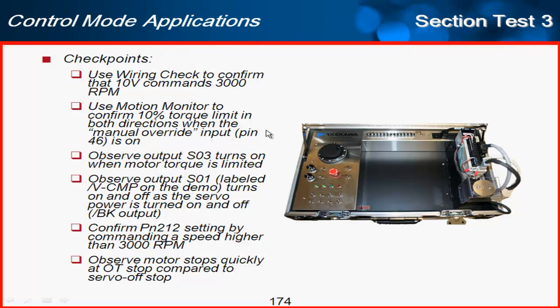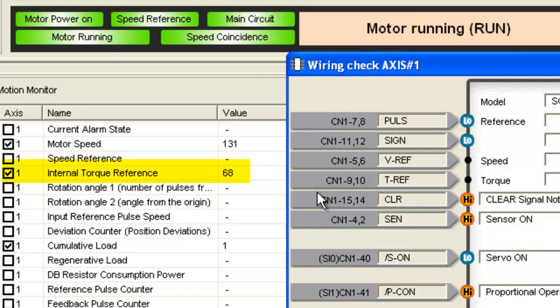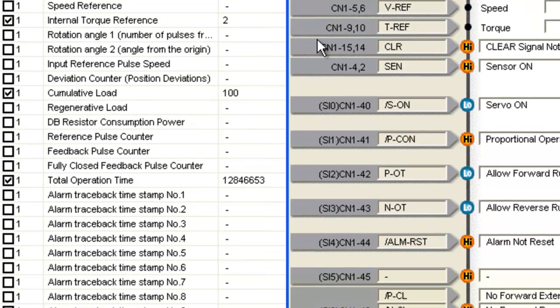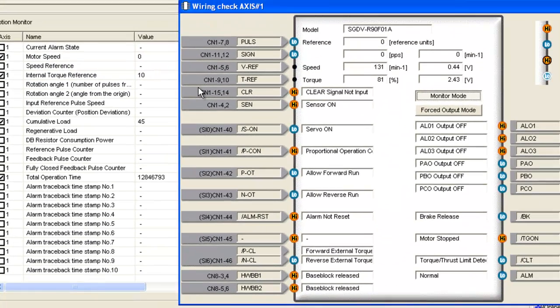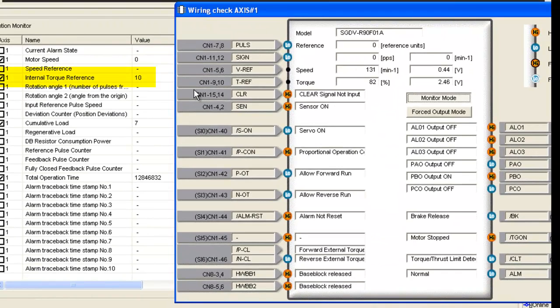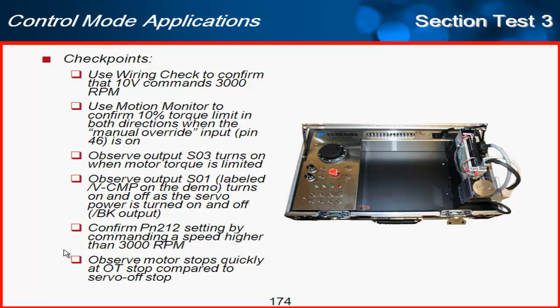I'll use the motion monitor to confirm that the 10% torque limit activates in both directions. I'll look at the internal torque reference with the motor running at a slow speed and apply torque. You can see the internal torque reference goes up high as I apply friction. But when I turn on pin 46 (PCL and NCL), the torque caps off at 10%, and the current limit output on the right goes from low to high — confirming it's working.